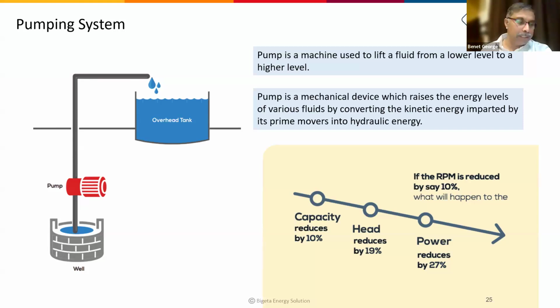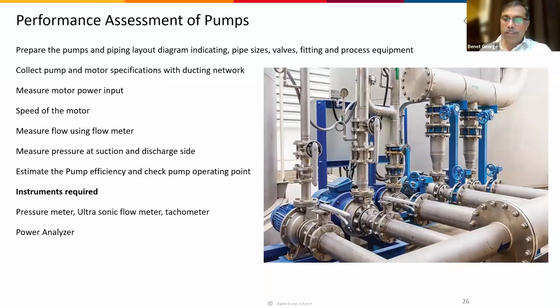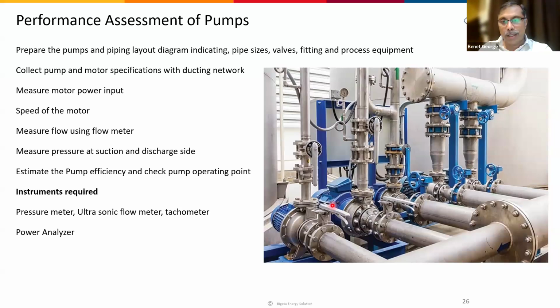So in the performance evaluation of pumps, you can see this is the pumping system. You can see multiple pumps, and you can also see valves on the suction and discharge sides, and pressure gauges and pressure transducers. These are all part of the pumping system. For a performance evaluation, we need to measure the pressure, the flow, and the power. These are the three requirements. Ideally we can have a flow meter, a power analyzer and a pressure meter, or in many cases a pressure meter may be available at site.